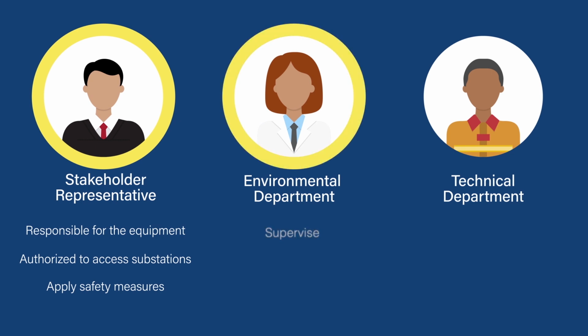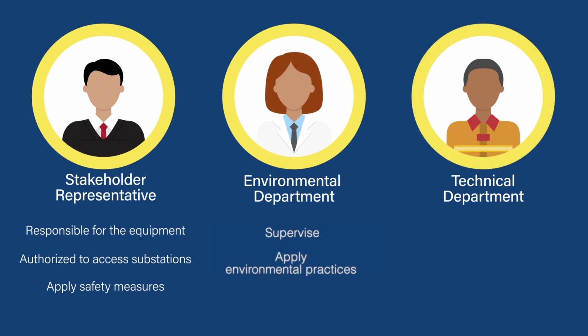The team member from the environmental department is responsible for supervision and to ensure that all procedures follow environmentally sound practices. The technical personnel: 2 electrician technicians will be responsible for the collection of samples. Both of them must be qualified to handle transformers when they are disconnected or connected to high voltages. One of them will be manipulating the valve. Meanwhile, the other technician holds a sampling bottle under the valve to collect 50 milliliters of the oil.